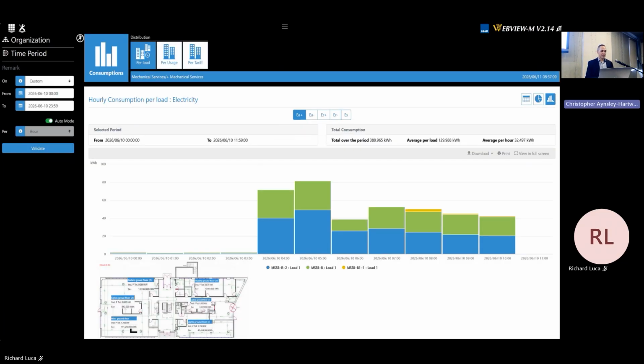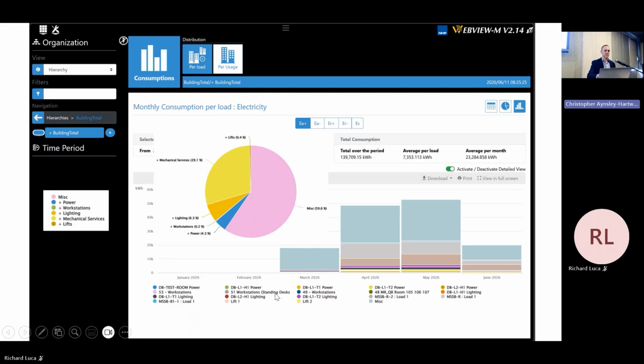Drilling down even further, we can see individual boards themselves. So someone might say, okay, are these boards in green? They're a lot less energy. They're the same boards, same loads. Why is it less energy than the blue? Is there blocked filters, broken coils, or is there something wrong with the HVAC compressor? We can put floor plans here, click on each individual section and drill down even further to the specific loads.